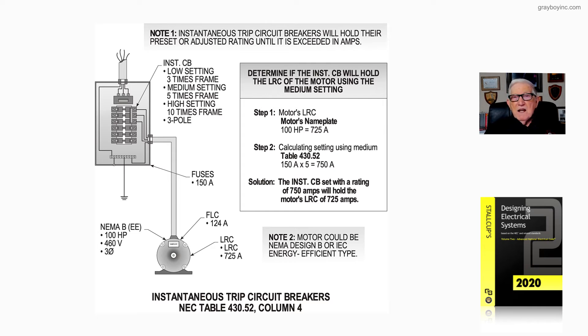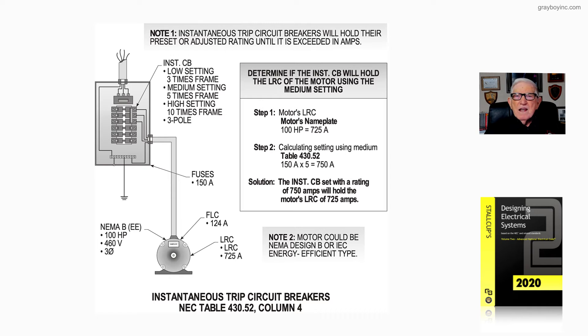Most of the time the overcurrent device sizing is mainly for short-circuit current and ground faults, allowing the motor to start. Notice the overload protection is not mentioned here, because you're sizing it greater than 125 percent of the motor nameplate, as required when we review 430.6(A) of the code.